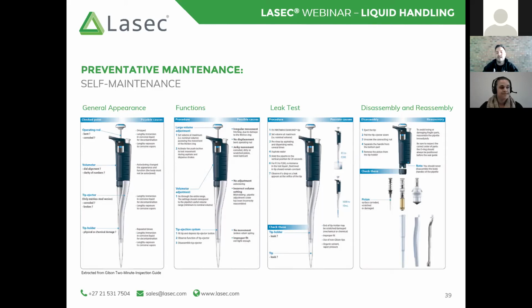So in a lot of situations, people prefer not to dismantle their pipettes. I find that it is generally a student sort of thing. We don't want inexperienced users damaging that pipette. But in saying that, if you do have any ingress of sample into your pipette or your tip holder, you want to prevent any corrosion of that piston. And the best way of doing that is to dismantle that pipette, clean out the tip holder sufficiently, let it dry, and then reassemble that pipette.